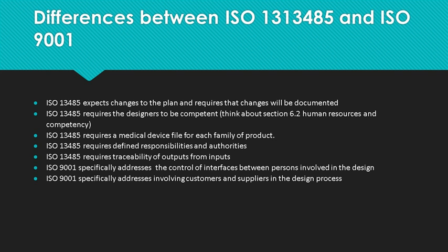The major differences between the two standards are that ISO 13485 expects changes to the plan and requires that the changes will be documented. 9001 doesn't reference changes to the plan. ISO 13485 requires the designers to be competent. Now, think about Section 6.2, Human Resources and Competency. This is where it's referring back to. I think ISO 9001 assumes that you will only have competent people. ISO 13485 requires a medical device file for each family of product. That's a requirement that is not anywhere in ISO 9001.